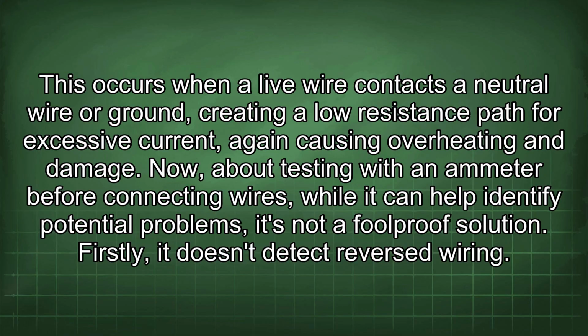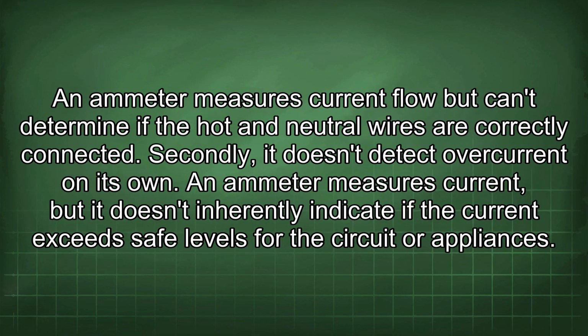Now about testing with an ammeter before connecting wires. While it can help identify potential problems, it's not a foolproof solution. Firstly, it doesn't detect reversed wiring. An ammeter measures current flow but can't determine if the hot and neutral wires are correctly connected.